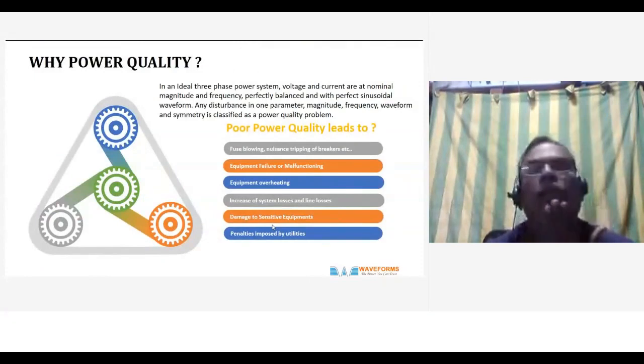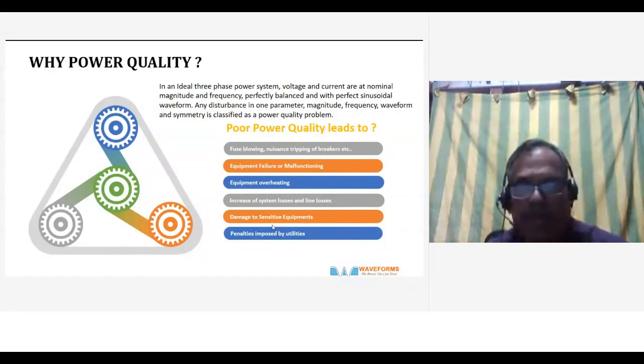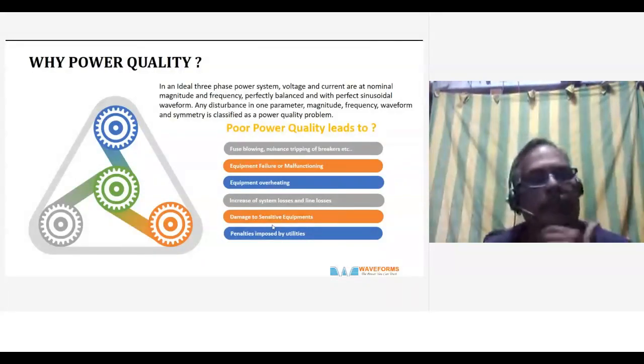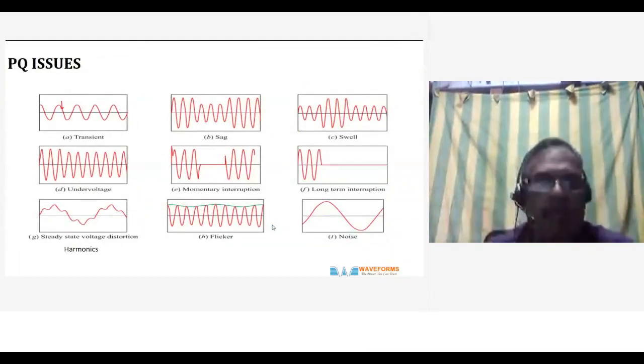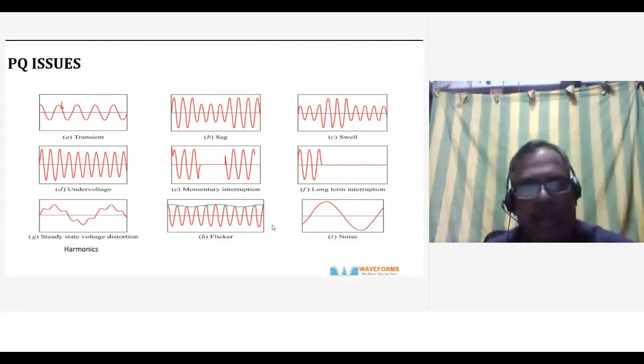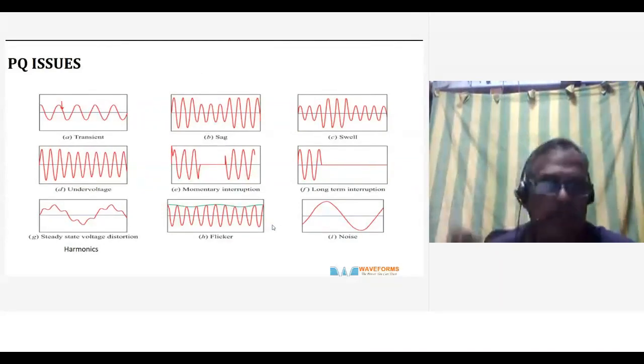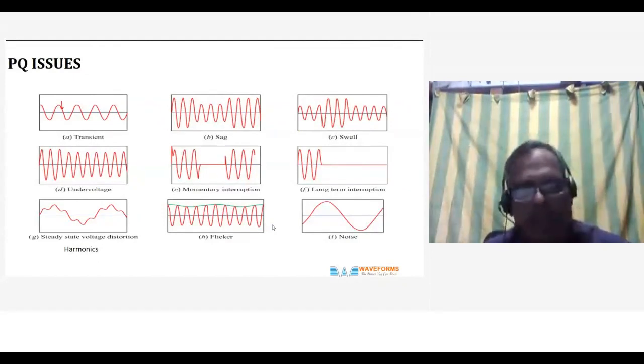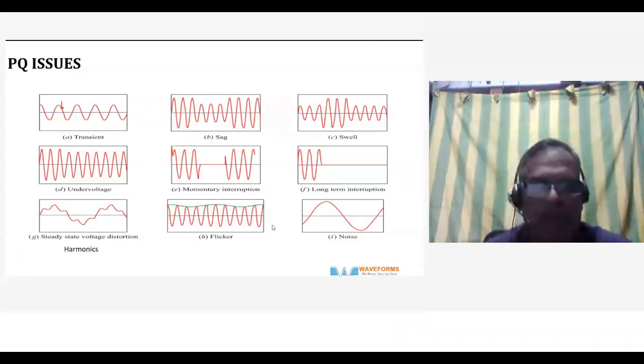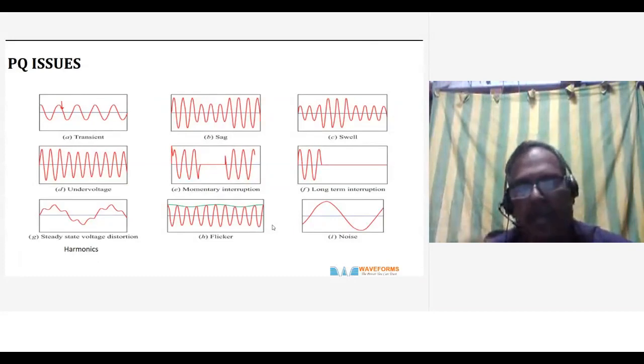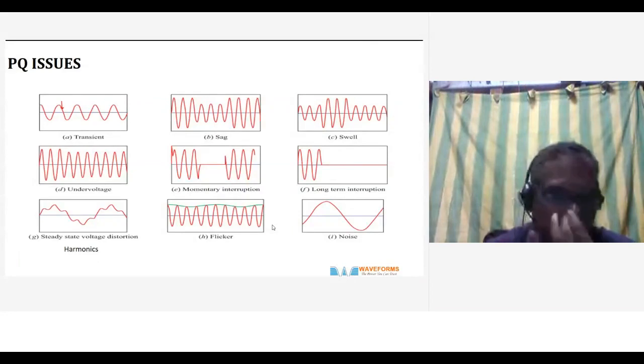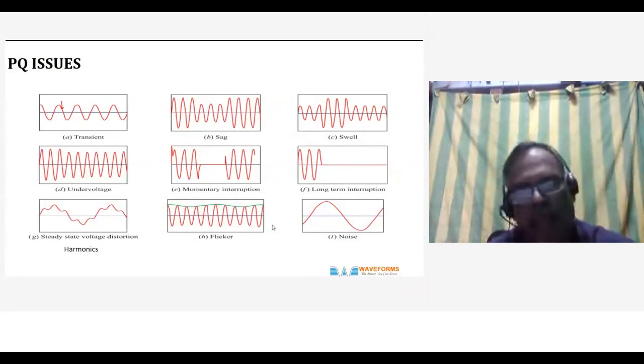Power quality is an all-encompassing term for power disturbances. You have various power disturbances, and everybody is aware of it: fuse blowing, nuisance tripping, equipment failure, malfunctioning, equipment overheating, system losses and line losses, damage to sensitive equipment, penalty imposed by utilities. So these are all the different PQ issues that you have. But transient, sag, swell, undervoltage, momentary interruption, long-term interruption, steady-state voltage distortion, which is harmonics, and then flicker and noise. But harmonics is the subject where cycle by cycle you have a problem. The other disturbances may occur infrequently, and that is something which can be solved quite easily. But when it comes to harmonics, it's a difficult subject. That's why we are focusing on that subject.